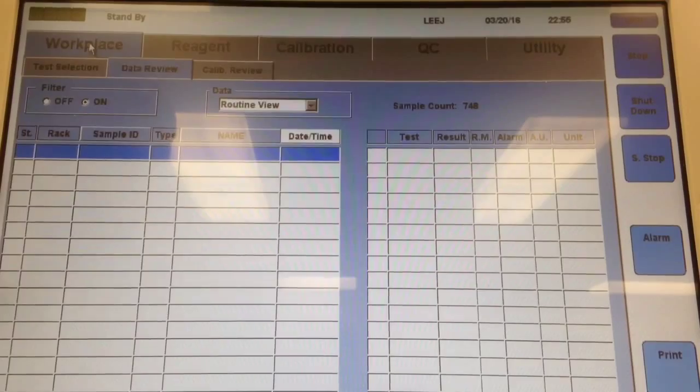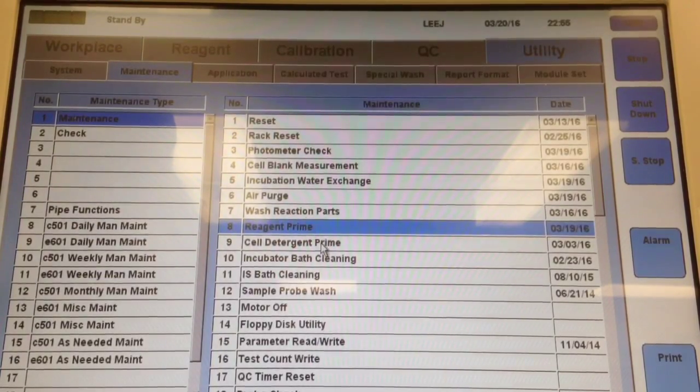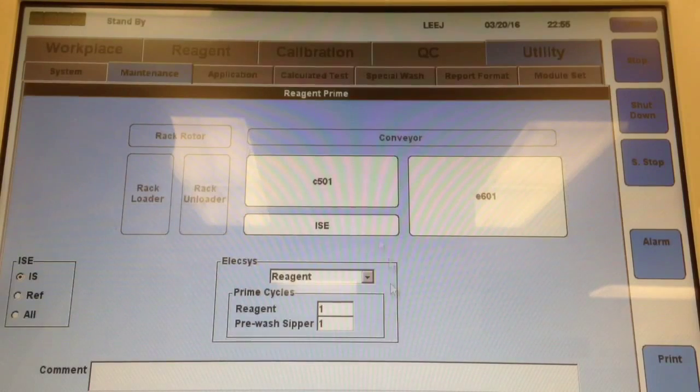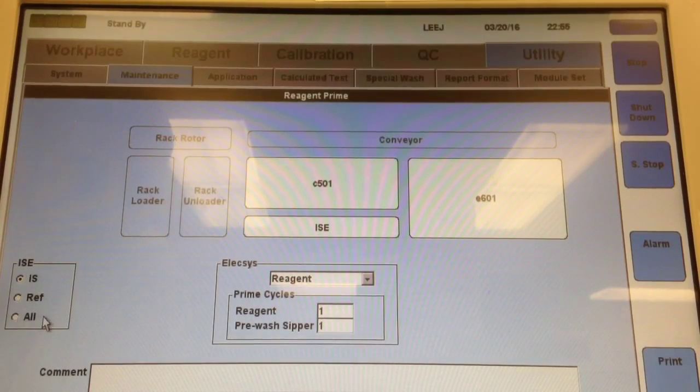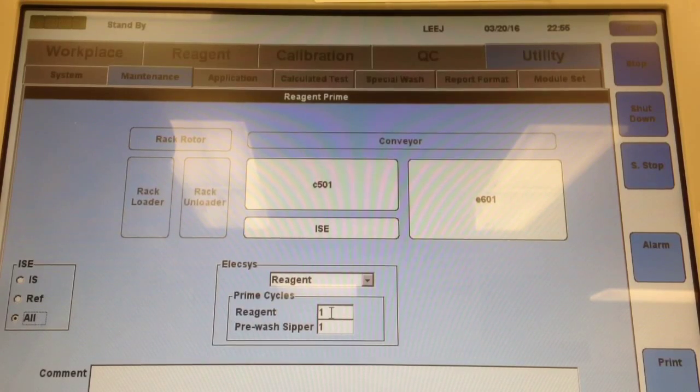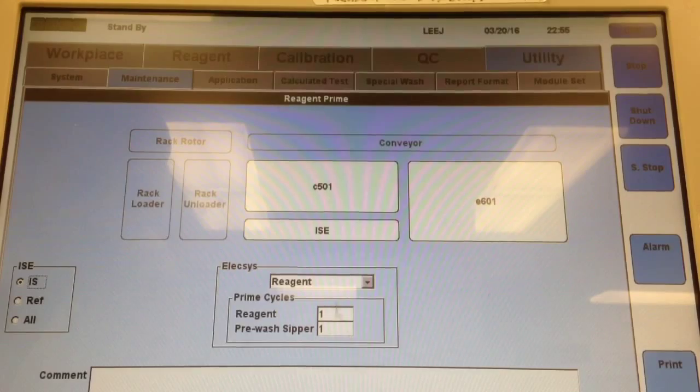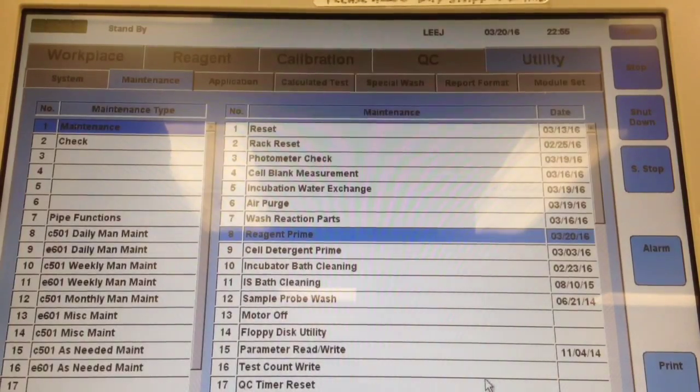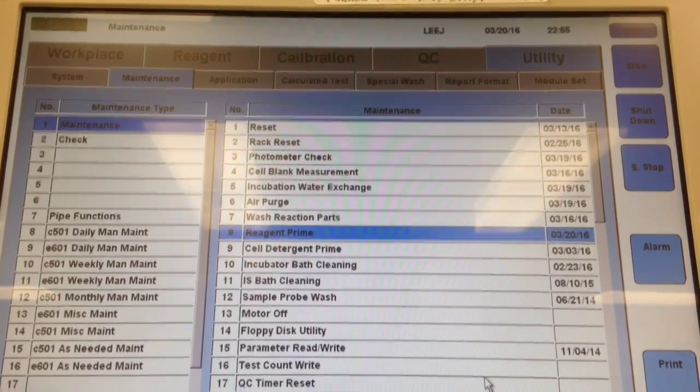Then we're going to go ahead and do a reagent prime. I'm just going to do one reagent prime in this video, but I am also later going to run the green rack and do the daily pipe, which will prime some more. Just go ahead and do however many primes you would like to do. One should be fine if you're going to do the other things. And that's all there is to it. Thank you for watching.